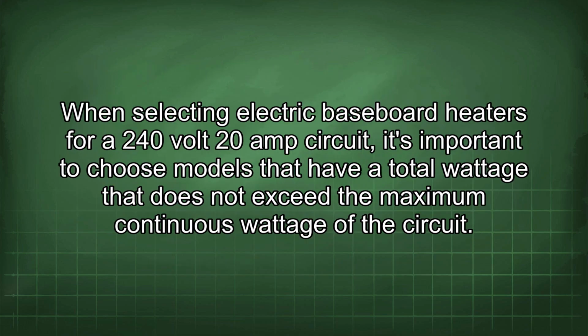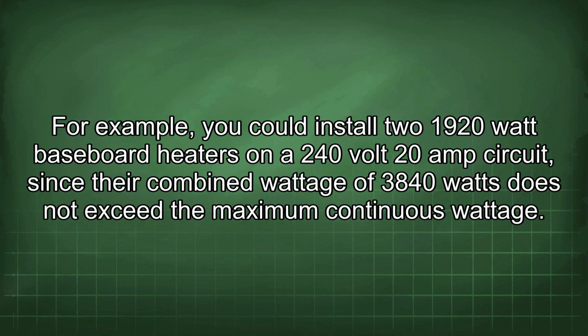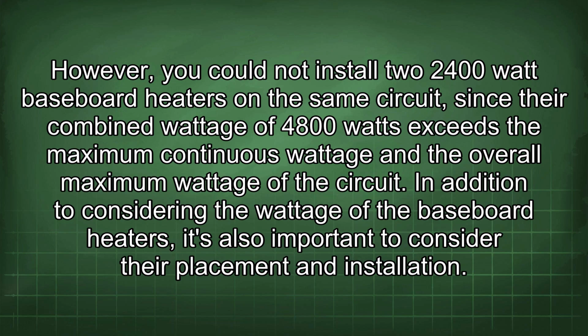When selecting electric baseboard heaters for a 240-volt 20-amp circuit, it's important to choose models that have a total wattage that does not exceed the maximum continuous wattage of the circuit. For example, you could install two 1920-watt baseboard heaters on a 240-volt 20-amp circuit, since their combined wattage of 3,840 watts does not exceed the maximum continuous wattage. However, you could not install two 2400-watt baseboard heaters on the same circuit, since their combined wattage of 4,800 watts exceeds the maximum continuous wattage and the overall maximum wattage of the circuit.